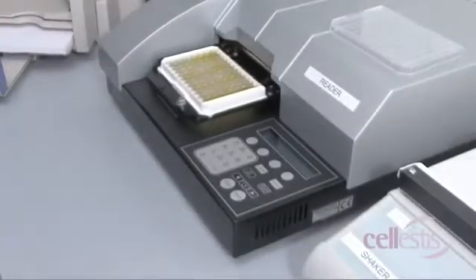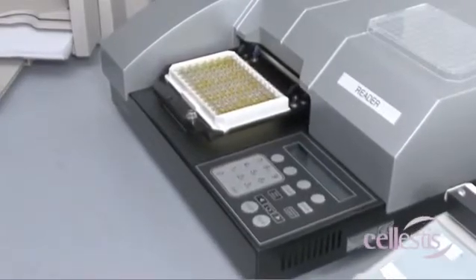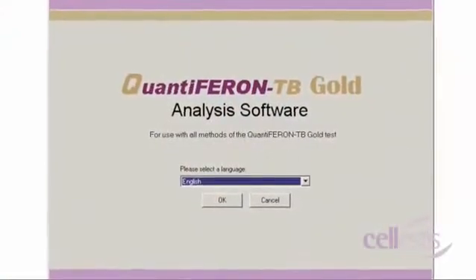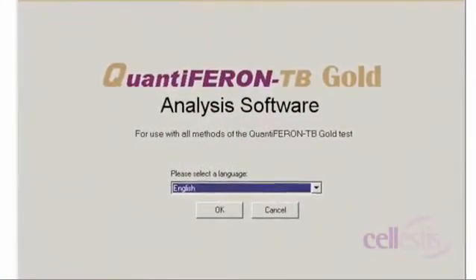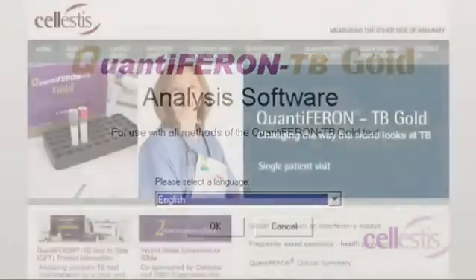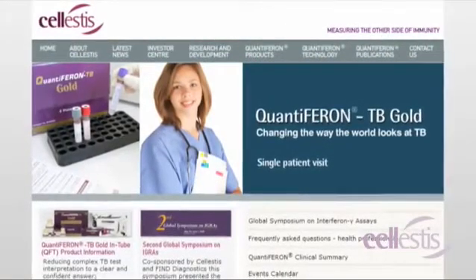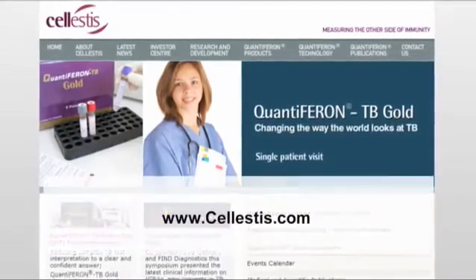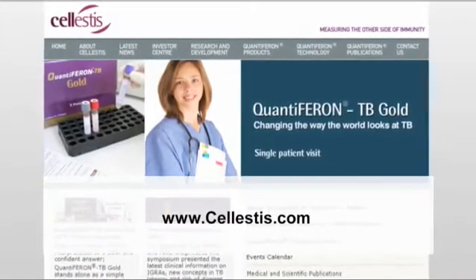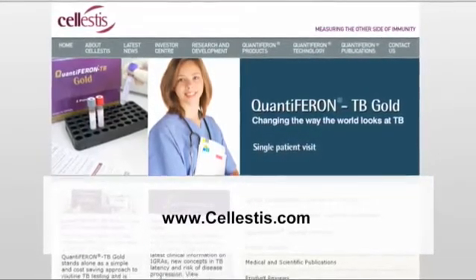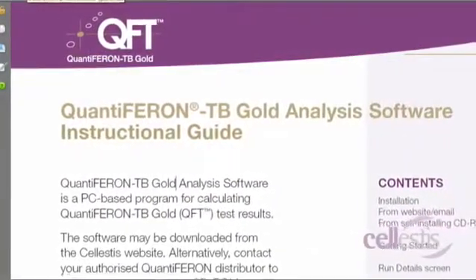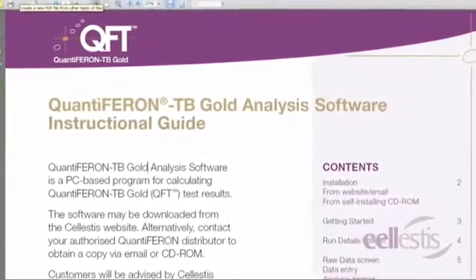Data is generated in Optical Density Values or ODs and is ready to be exported to data analysis software. The QFT analysis software provided by Cellestis is one of several data analysis tools that can be used. A copy of the latest QFT software can be obtained from the Cellestis website at www.cellestis.com under QuantiFERON-TB Gold In-Tube Technical Information. For step-by-step instructions, please refer to the QFT Analysis Software Instructional Guide available on the website.